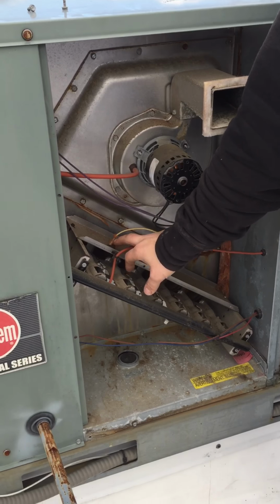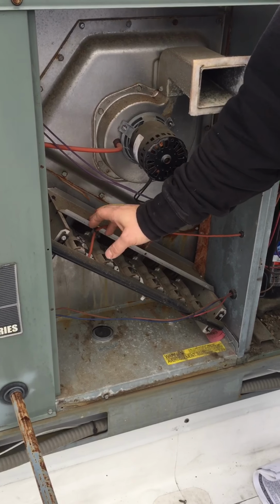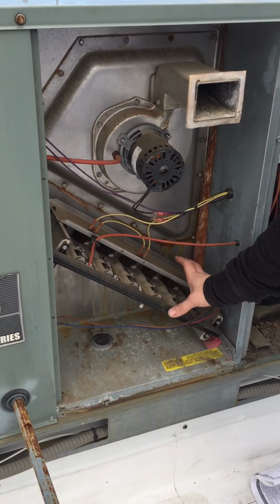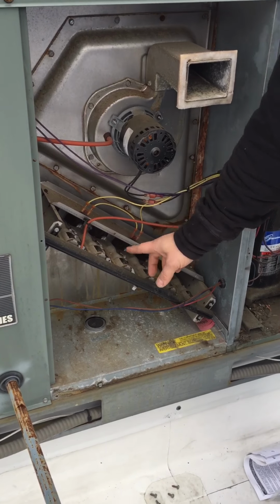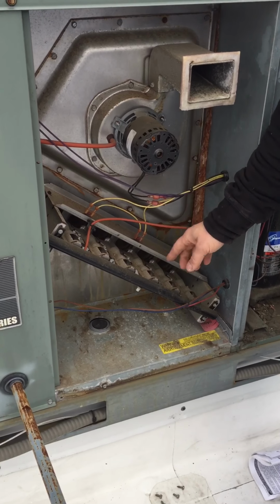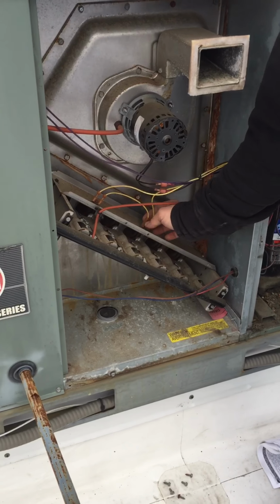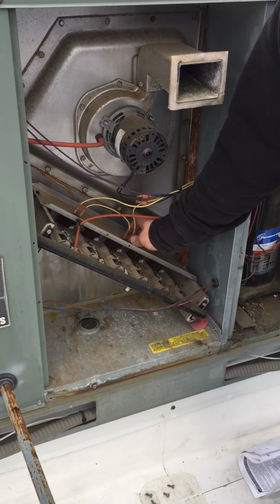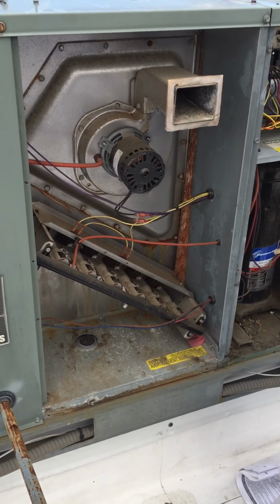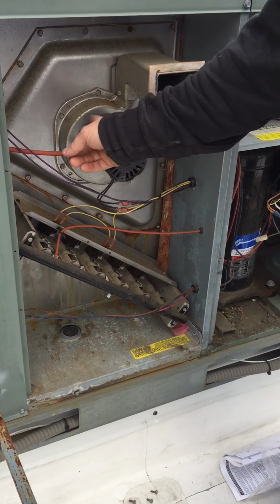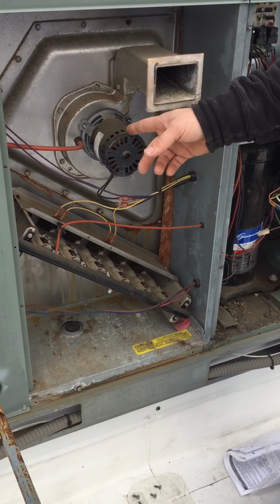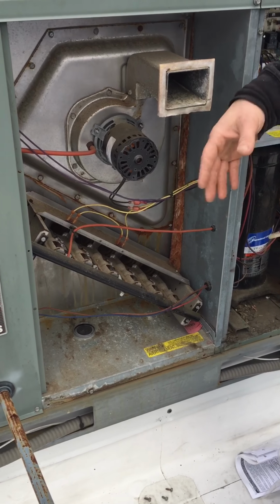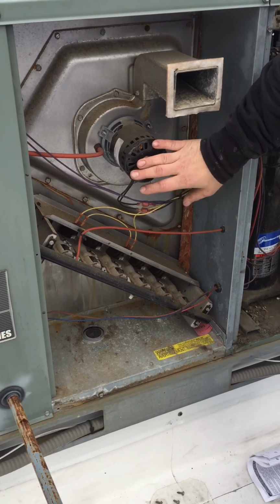It's not split, so you're not getting any carbon monoxide. This is a high temperature safety device for this section right here. If these flames aren't getting pulled through those tubes, it will overheat this top panel and pop this. So the only other thing that could cause that would be this: on the back of the impeller there's a wheel, a squirrel cage. I pulled this whole motor off to check it and it's fine. Sometimes the blades will fall off, but the blades are fine.